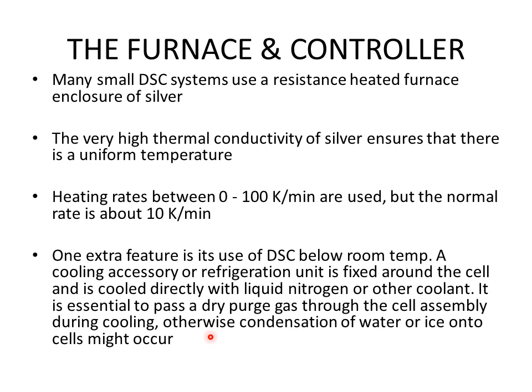If dry purge gas is not used during cooling mode, condensation of water or ice onto the cells may occur.